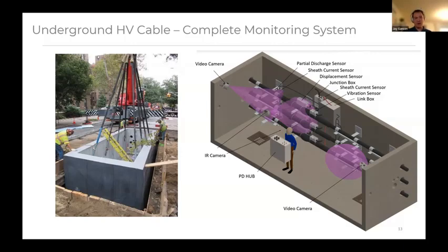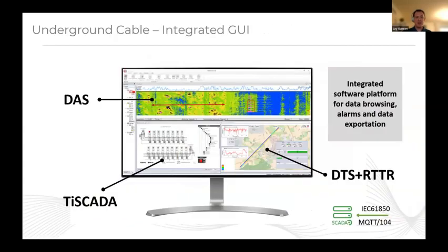In addition, we've worked with partners on this project to bring in other elements. While all of the information that we provide through PD, vibration, and displacement comes into a single dashboard called TiSCADA, we also work with partners that provide DAS and DTS, which is distributed acoustic sensing and distributed temperature sensing. The temperature sensing is really interesting because it allows you to use a real-time temperature rating on the cable itself. So you can have a really good understanding of proper loading and get excess capacity through the system without exceeding thresholds. And the distributed acoustic sensing will pinpoint if there ever is a failure on a system. It will tell you exactly where that failure happens, which can speed up your time to recovery.